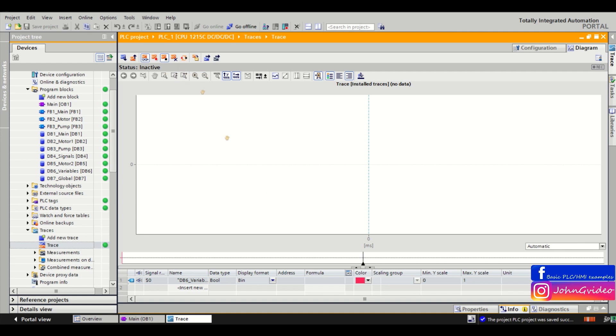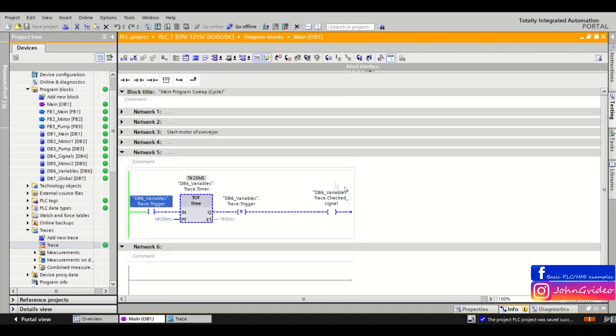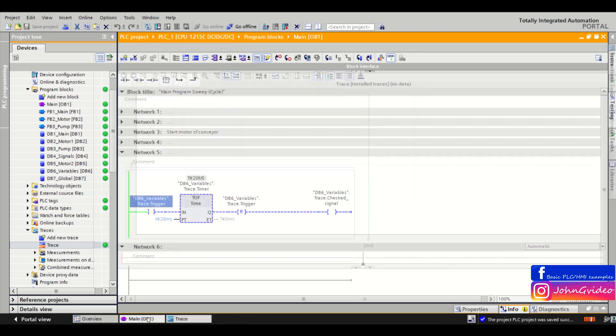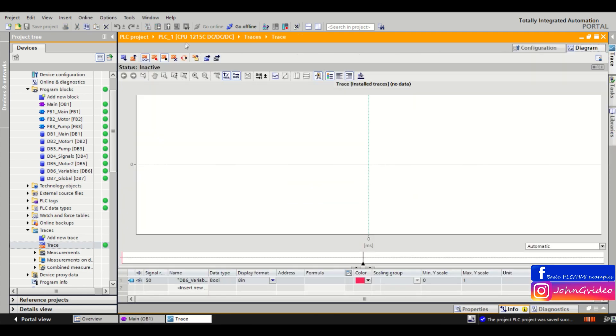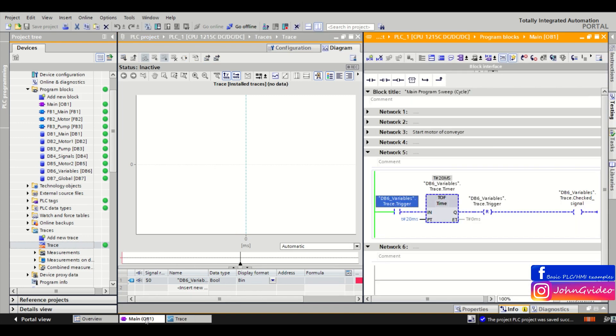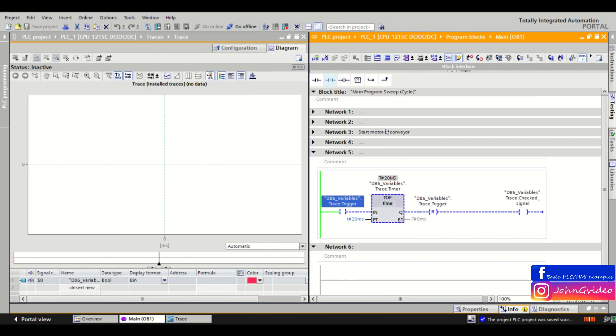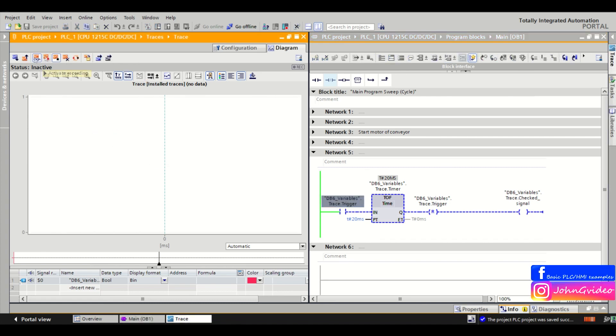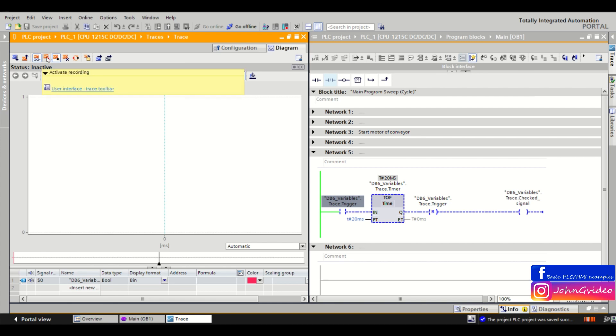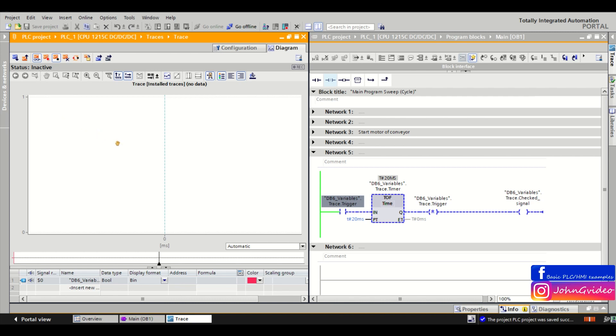Now we transfer it and here in the graph we see when our checked signal variable was set to true. So now we go online. When I click on activate recording, then we start to record these 58,000 samples where every sample is one cycle of the PLC.